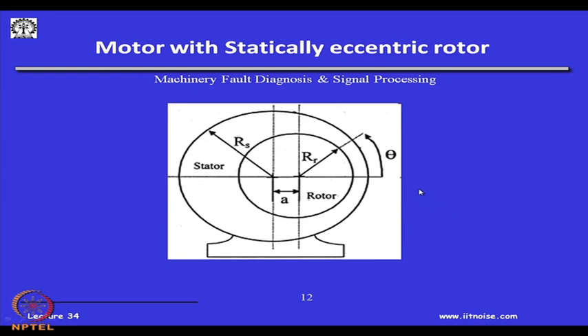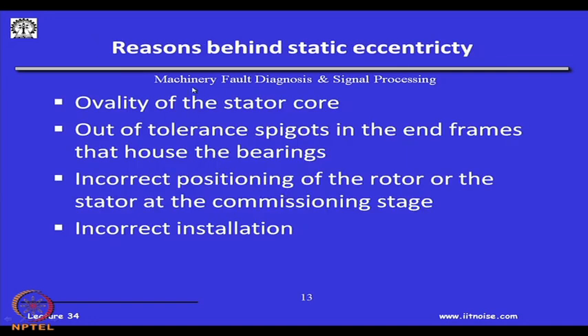There could be cases where the motors could have a static eccentricity. This is the rotor, this is the stator, this has been exaggerated here, and they have an eccentricity A. What are the possible reasons behind this static eccentricity? One is the stator core is not a perfect circle, but oval. Out of tolerances at the end frames that house the bearings. So, bearings themselves are not aligned. Incorrect position of the rotor or the stator at the commissioning stage. Many times the rotors are so heavy that they have to be put right at the site, they have to be installed, and there could be an incorrect installation. One foot is at a higher ground than the other, and there is an angular deviation. So, all these lead to the static eccentricity between the rotor and the stator, and because of this eccentricity, there will be an air gap variation.